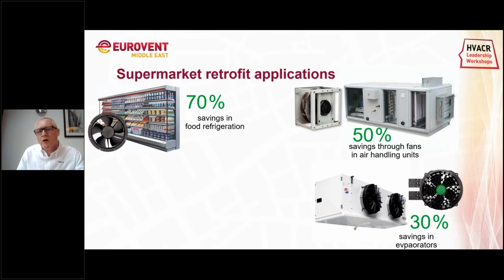One of the things we have been working on is the aerodynamics, like I said previously. So as you can see from this slide, it's got a diffuser built into the actual EC fan. We've got quite a few different products with air diffusers, which means you can get greater airflow. Then potentially, if you run it with a door curtain, maybe sometimes during low usage, you could reduce the speed slightly to maintain it, and that'll give you a nice constant refrigerant pressure as well.